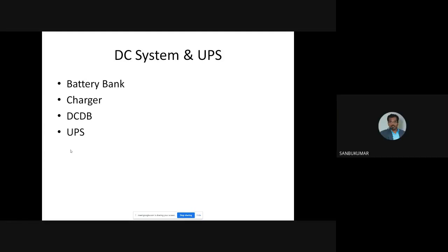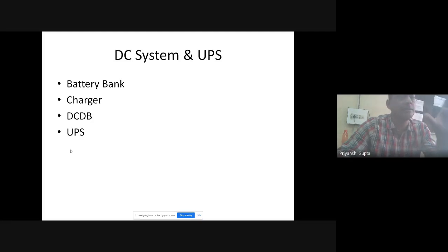All the protections, all the relays protecting the switchgear, including transformers and transmission lines, for any fault in the cable, are charged with the DC supply. The DC system also contributes to emergency lighting. So if the DC system fails or is not able to meet demand, we lose all the protections. If protection is not there and any fault occurs during that period, it will lead to major damage. Major damage means you lose money, you lose your capital equipment, and everything gets damaged. So protection is very important in that way. The DC system and all the UPS are very important.